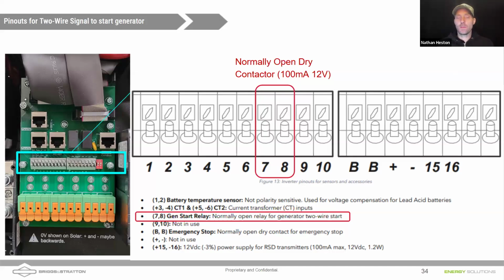So there's some nice things about this. You save fuel, you reduce run time on the generator, it's going to last longer, and there's less maintenance on the generator. And so you would use pins 7 and 8 to automatically start up the generator. That's a dry contact, and those are normally open pins. What do we mean by that, Daniel? What's a dry contact? That it's going to simply close when it calls for the generator to start.